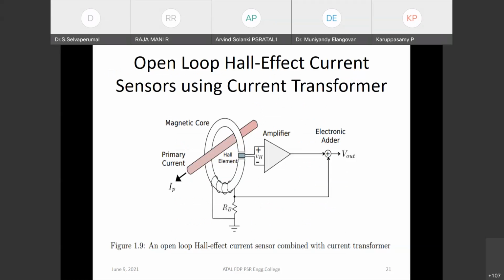So in open loop current sensors, the Hall element is solely responsible for measurement of both low and high frequency primary current. Its performance gets damaged at high frequency due to thermal drift, non-linearity, and limited bandwidth of the Hall element and the amplifier circuit, right?